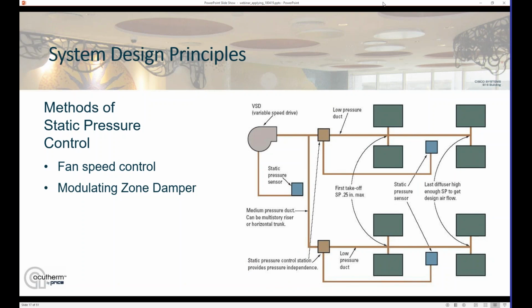So another method is a part medium pressure, part low pressure system using modulating zone dampers. In this approach, we've designed the low pressure duct sections similar to before, in that pressure at the last diffuser is high enough for design airflow, and pressure at the first diffuser is no higher than the 1/4 inch. But now we have the static pressure sensor feeding back to a modulating zone damper. This could be an Acutherm PIM module or pressure independence module, or a converted VAV box, but a damper with a controller such that when the diffusers close toward their minimum, that damper can close down and prevent the pressure from building up. And again, when the diffusers open up again, the damper opens up, providing the air they need to supply the spaces.